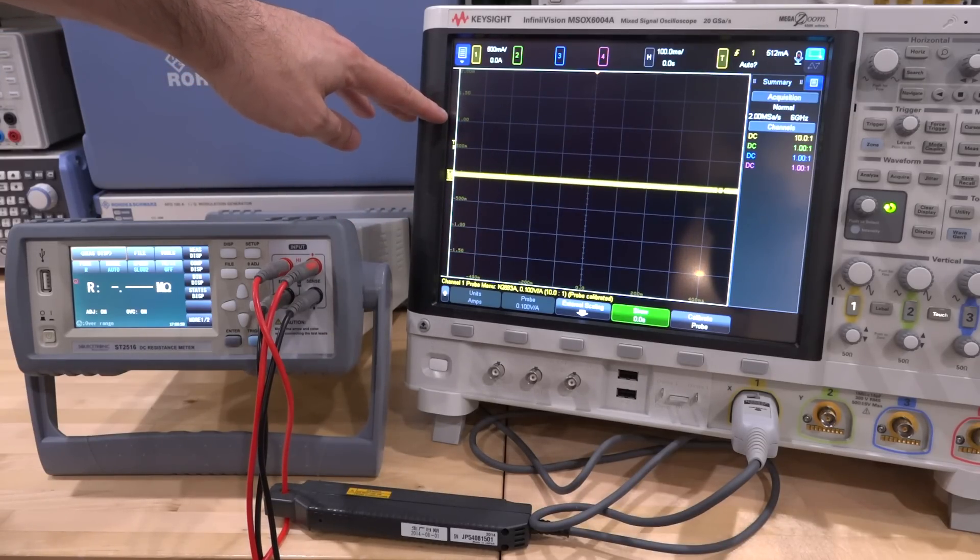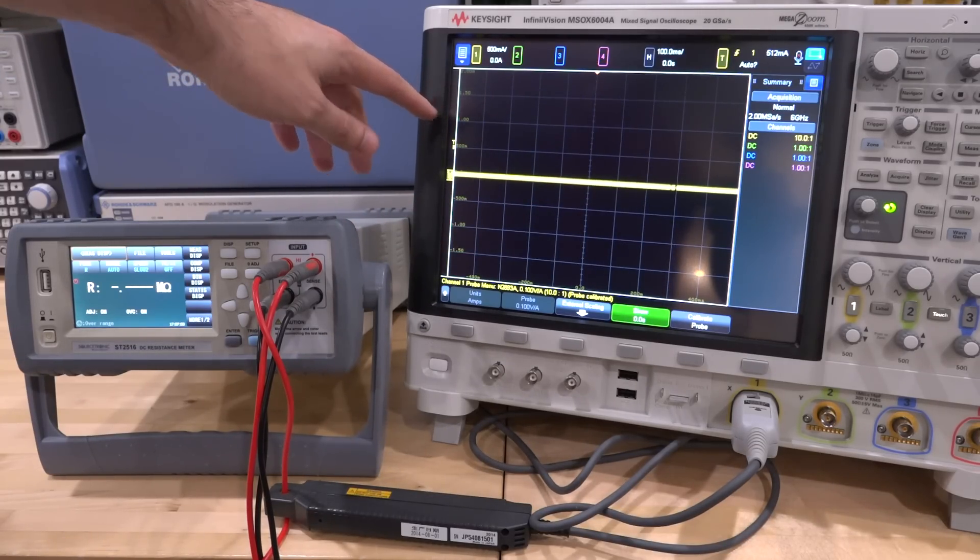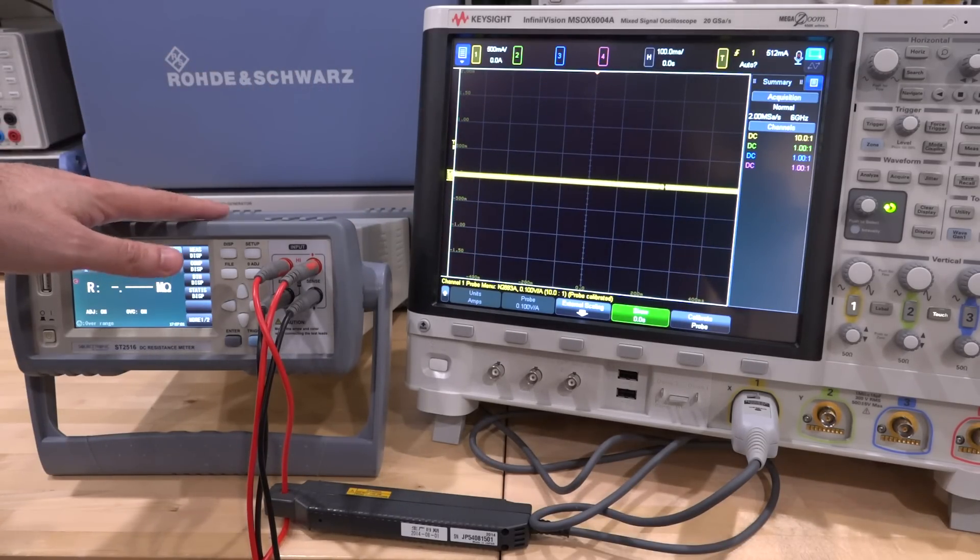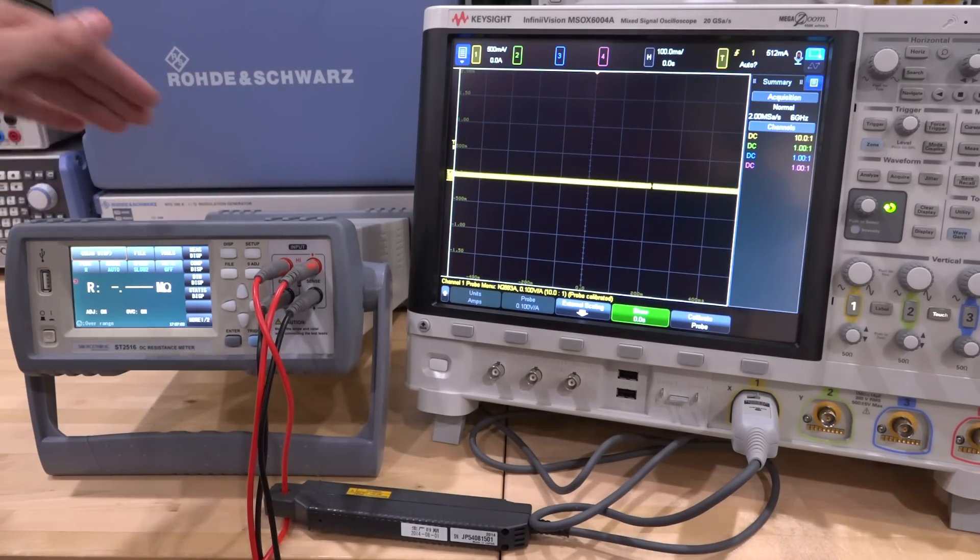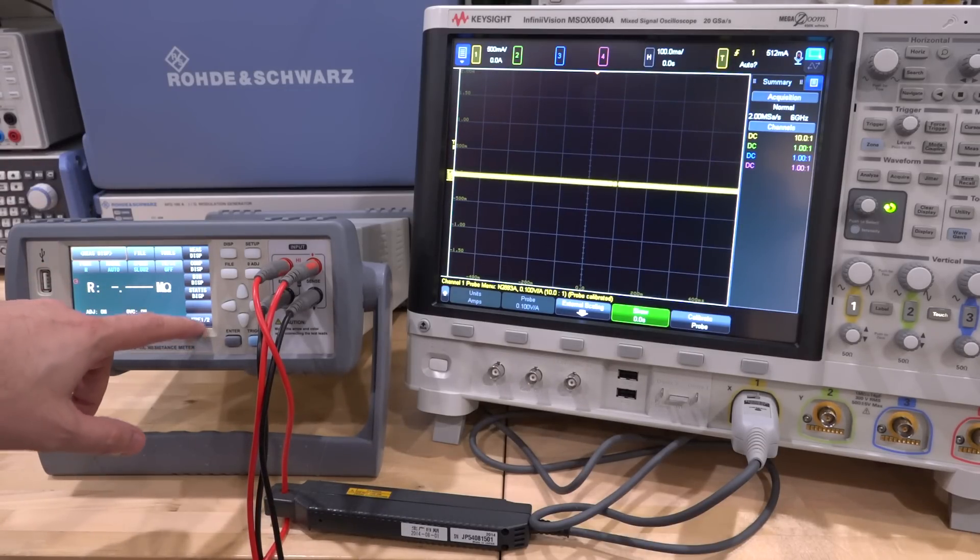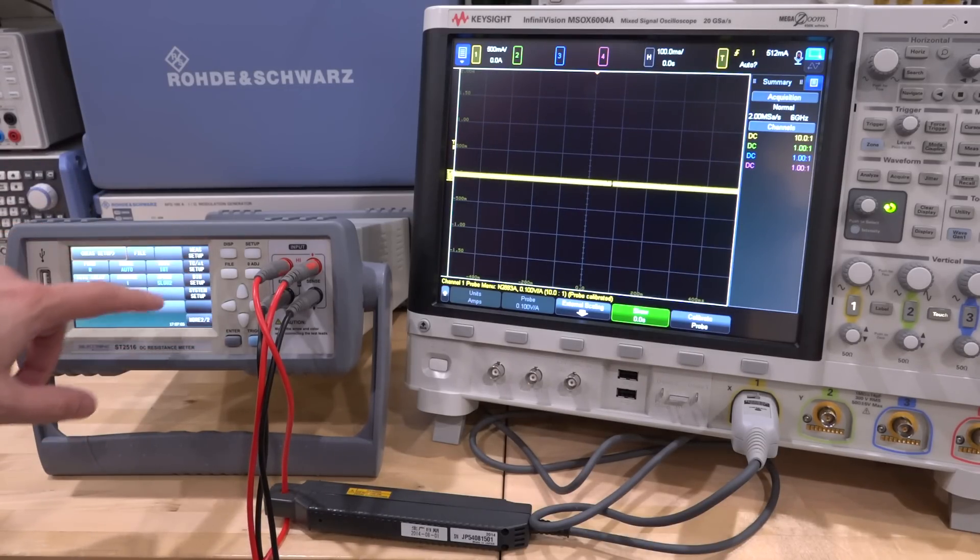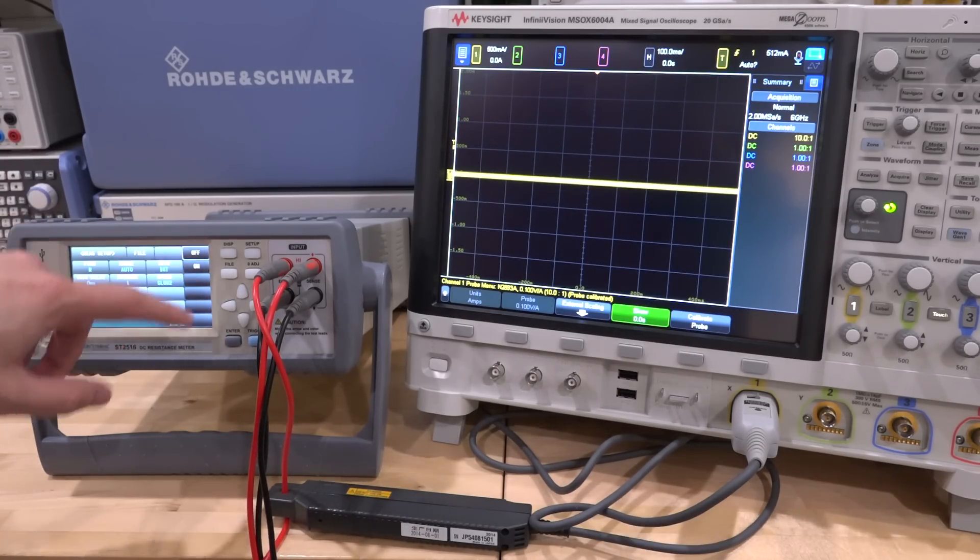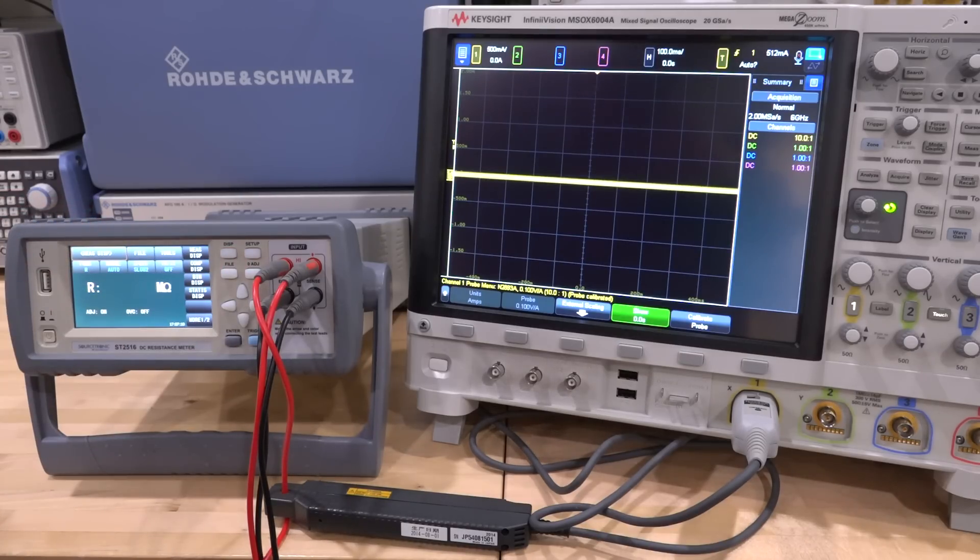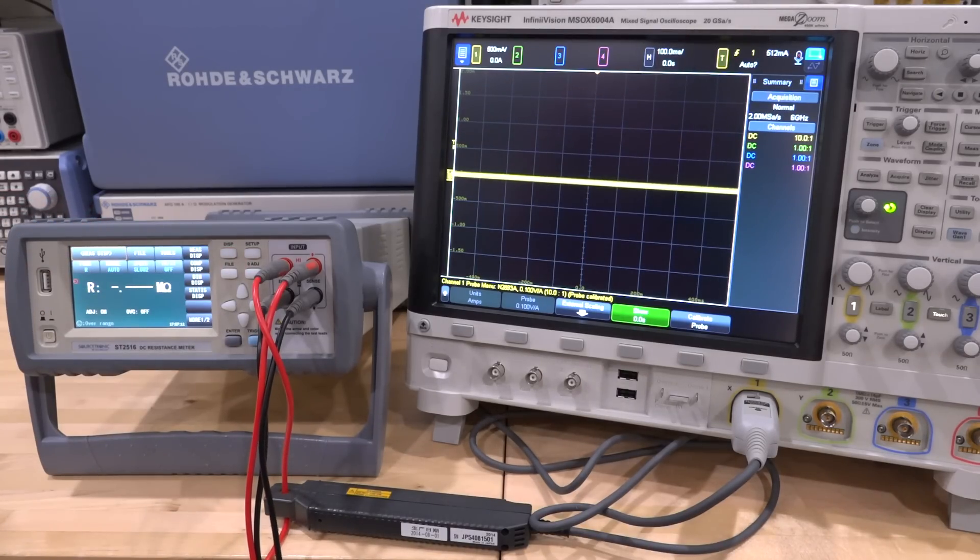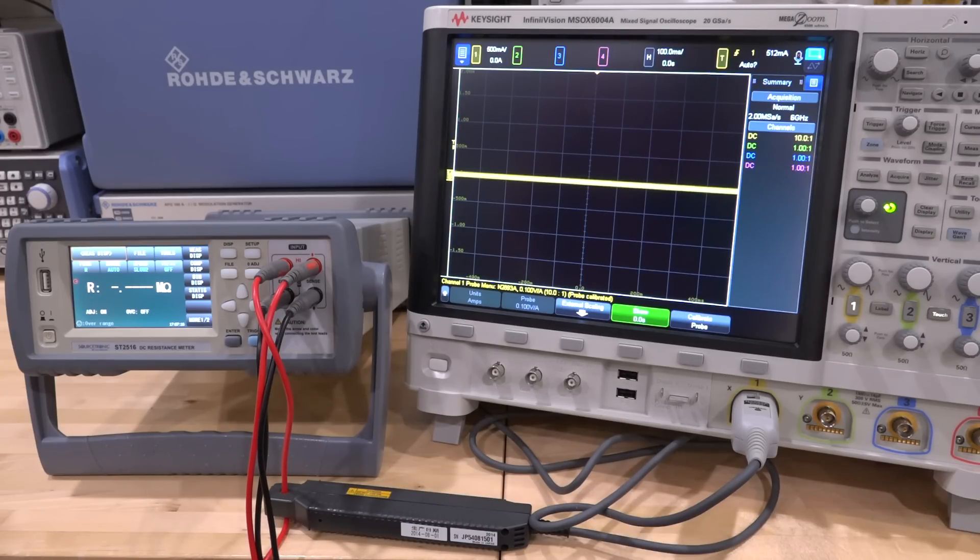And right now there's nothing connected so the current is sitting at zero. Now this line over here at the top, this is one amp and we know that this instrument is capable of delivering a maximum of one amp. So first thing I'm going to do is I'm going to go over here, I'm going to turn off the OVC. So there's no correction being done there.